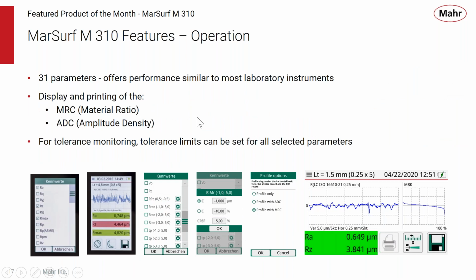Now with the M310, there's 31 parameters that offer performance similar to most laboratory grade instruments. You can also display and get printouts of material ratio curves or amplitude density curves. Those are types of features that are used often with bearings or parts being used interactively between them to ensure that the surfaces will perform together as they're expected.